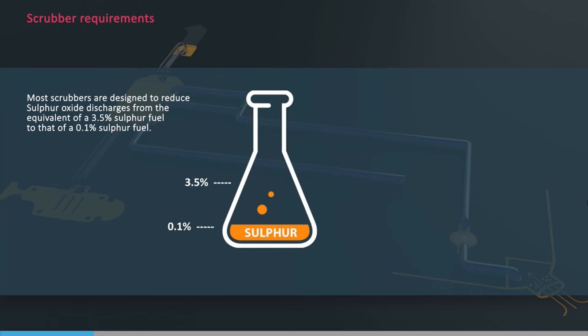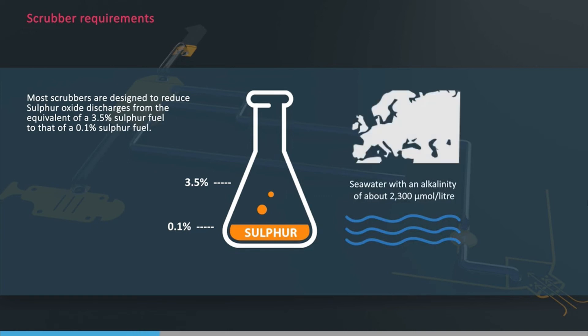For open-loop scrubbers, this would be when using seawater with an alkalinity of about 2300 micromole per litre. This covers the North Sea area excluding the Baltic Sea, where the seawater's low alkalinity may reduce efficiency.